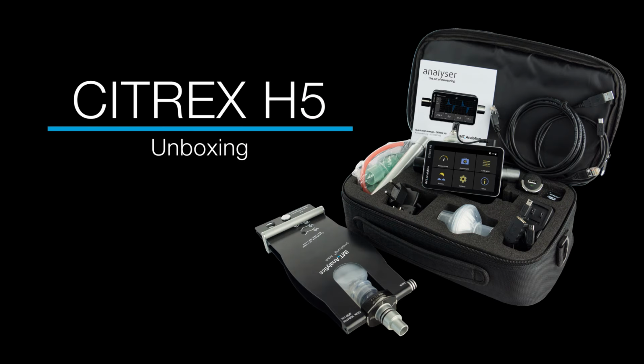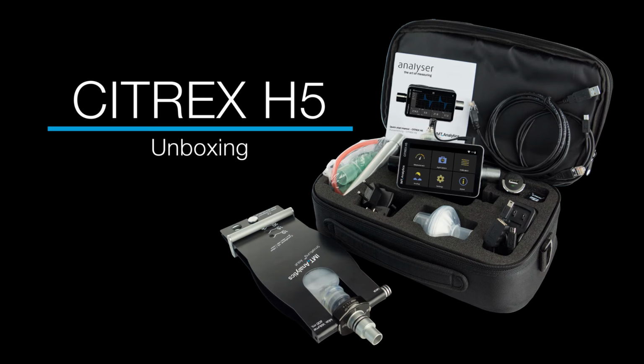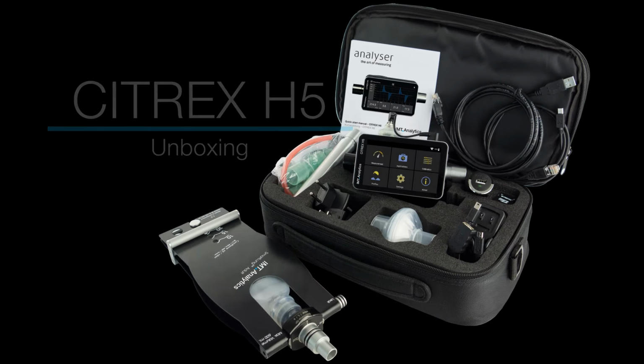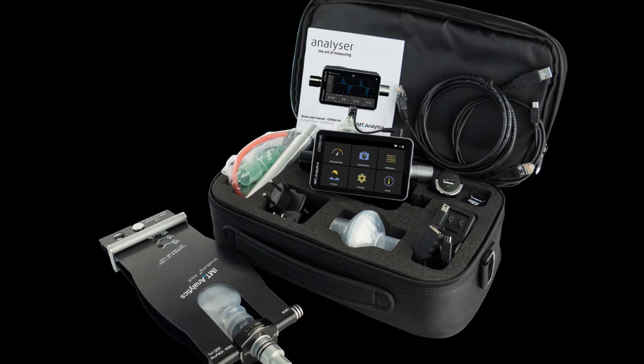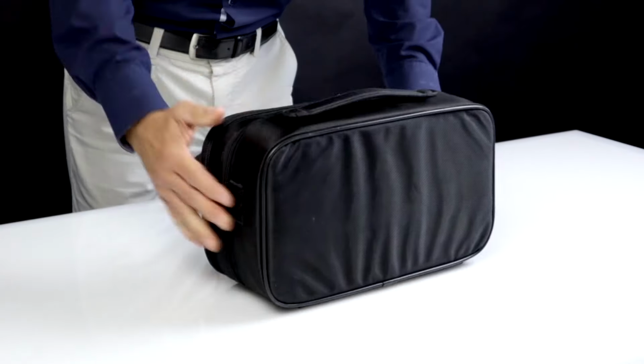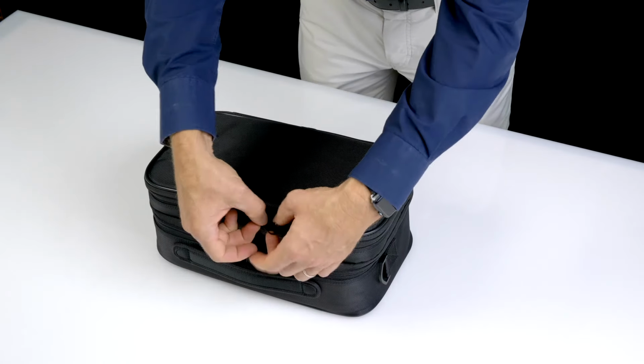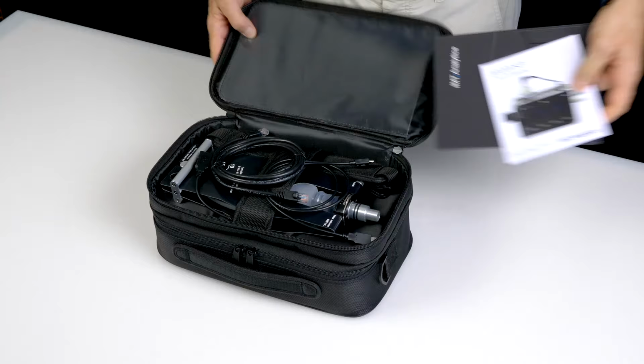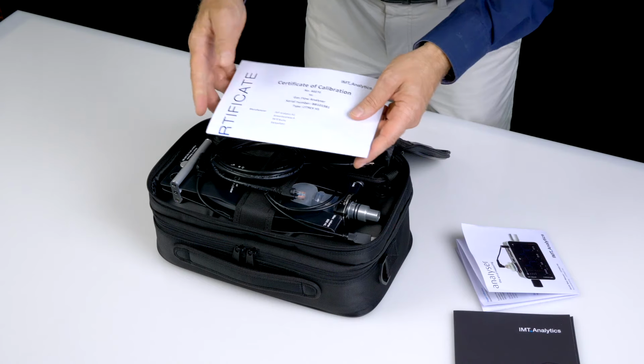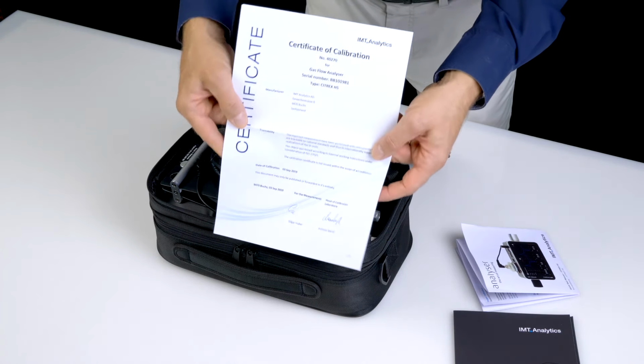CITREX H5. The high-precision measuring device CITREX H5 is the ideal solution to check and calibrate gas flow and pressure-generating devices in the medical field. The test set contains a compact bag, enough space for secure transport, a quick start manual which explains how to set up the device, and a detailed calibration certificate.